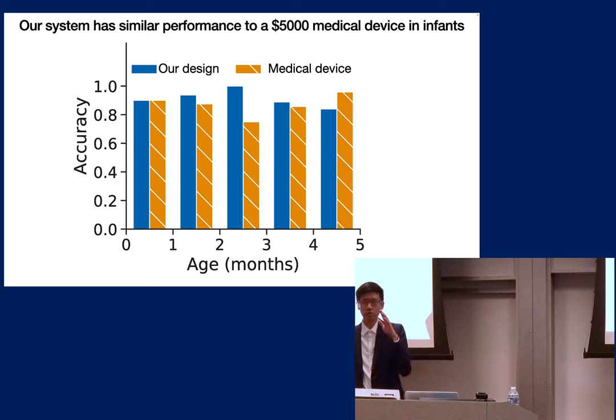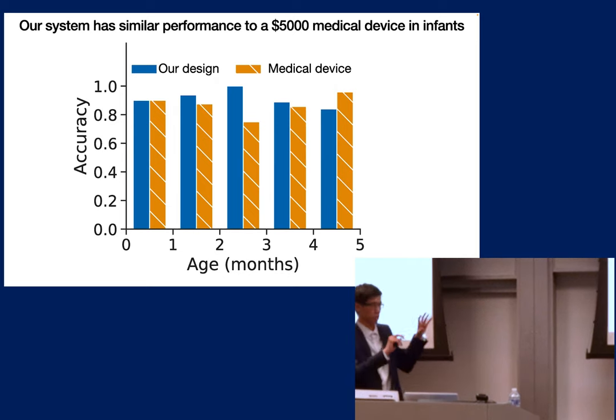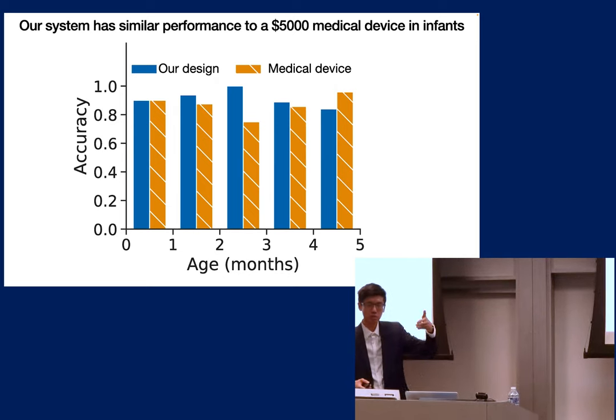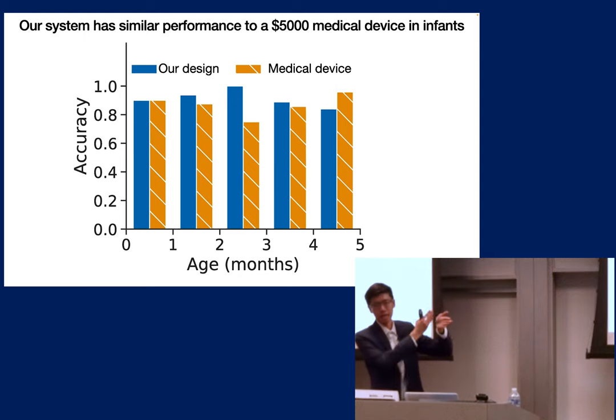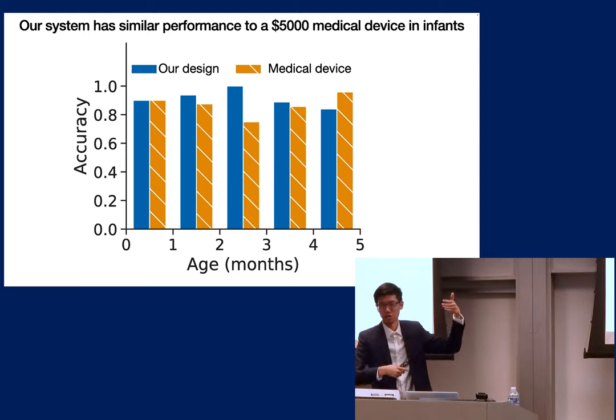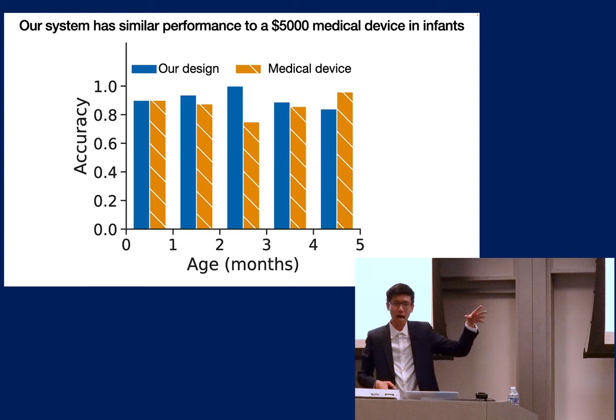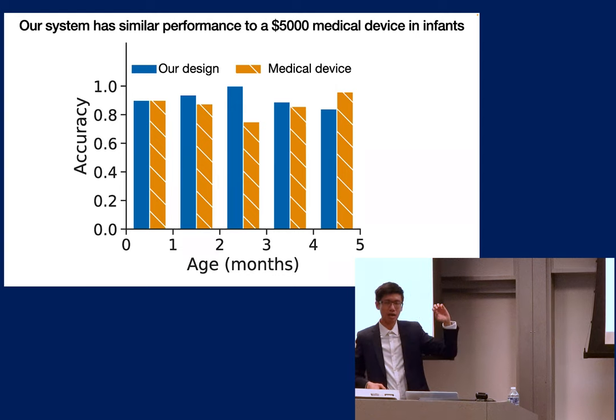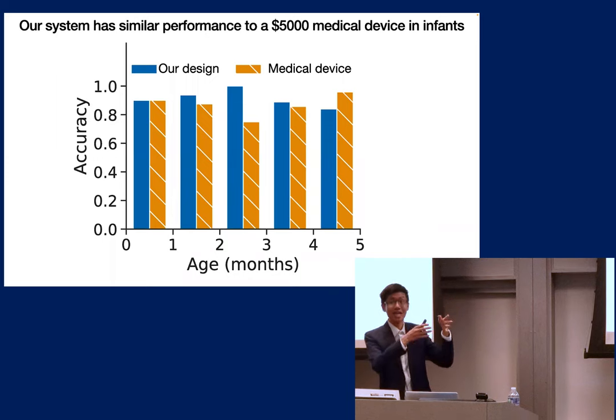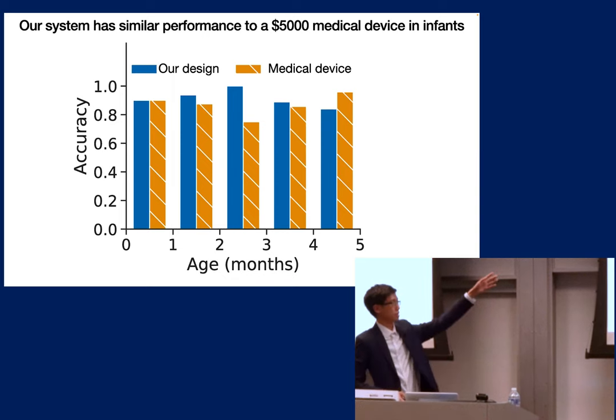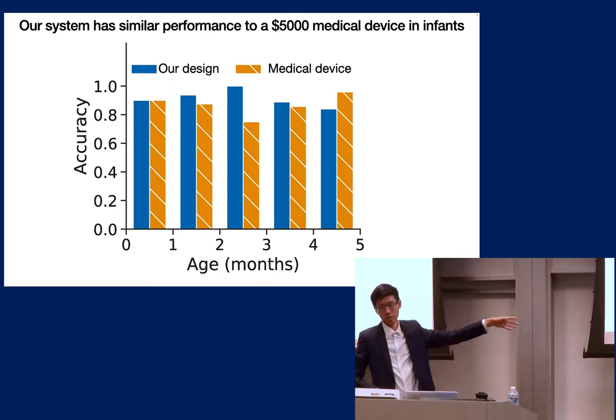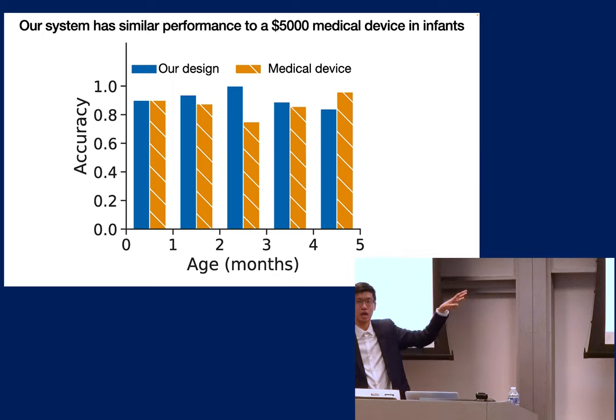The way we came to this result: typically when you do the test, you get a signal to noise ratio at 5 bands - 1, 2, 3, 4, 5 kilohertz. As long as each band is above 6 dB, that's a pass for that band. If you have 3 bands or more that pass, the test passes. We use that to calculate this accuracy, and that's what was done for the clinical device as well as this device. That's how you calculate it.